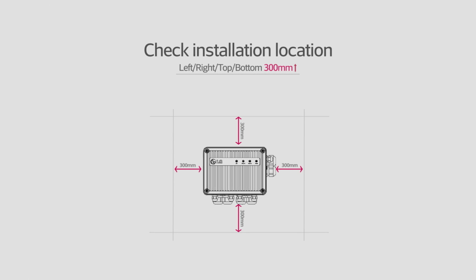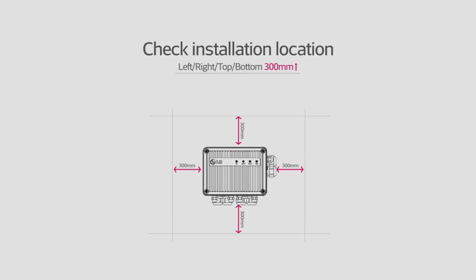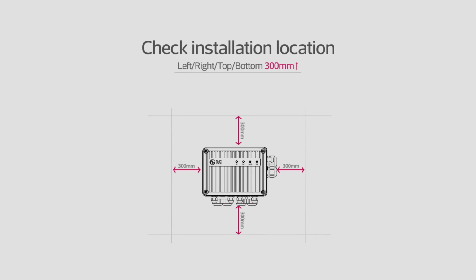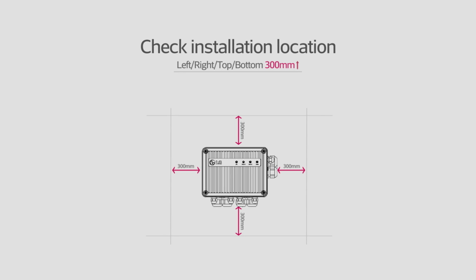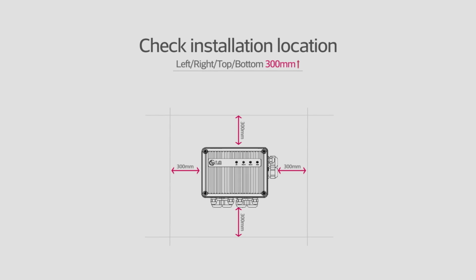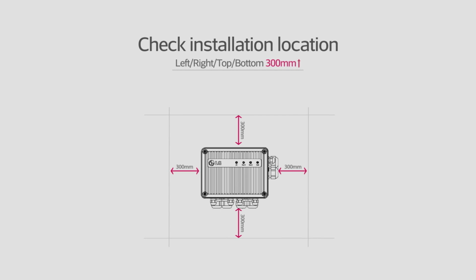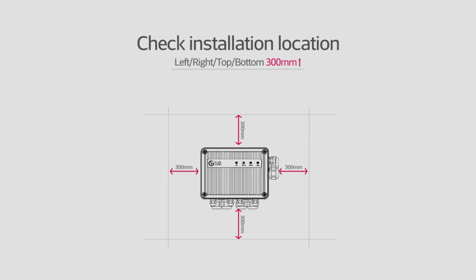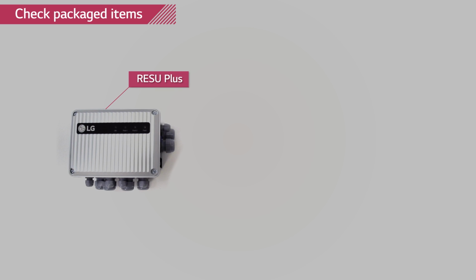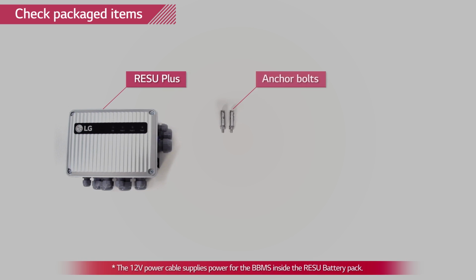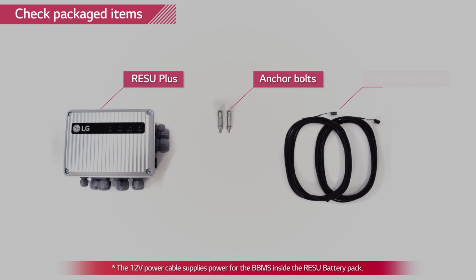Once you have picked the spot which meets all the requirements for the installation environment, put on safety gears listed in the installation manual. Spaces for 2 RESU packs, 1 battery inverter, and 1 RESU Plus should be reserved prior to the installation. Check every component of RESU Plus package. In the package, you will find RESU Plus, 2 anchor bolts, and 2 12-volt power cables.